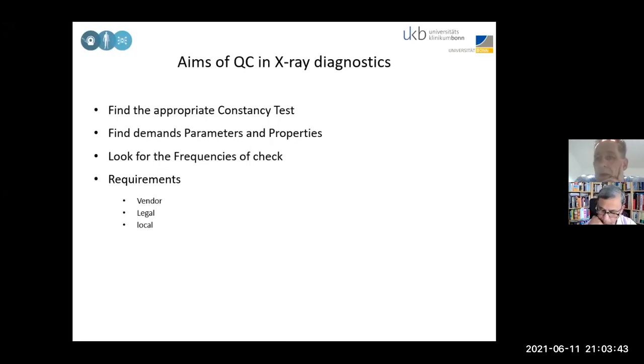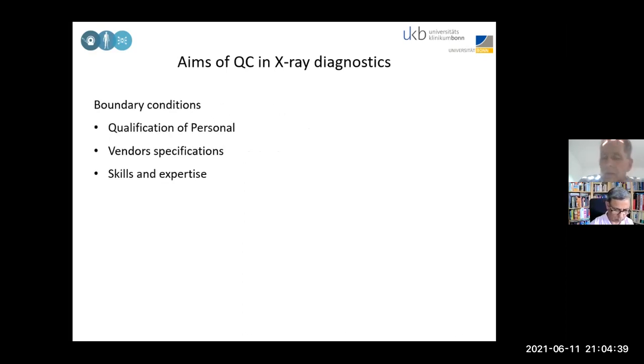And a very important part is the third point, look for the frequencies of the check. So what, when, or how often do we have to do that? And sometimes you ask yourself, why do I have to do it every day? Or why do I have to do it quarterly, or biannual, or semi-annual, or annual? And some of those frequencies are actually demanded on legal basis, but nobody tells you on legal basis you have been asked to do it annually. You can do it also semi-annually and check those. This is definitely not forbidden. And if you feel more secure looking at some parameters in a shorter frequency, why shouldn't you do that? It's not forbidden, but the minimum requirement, checking annually, is most likely given via legal requirements.